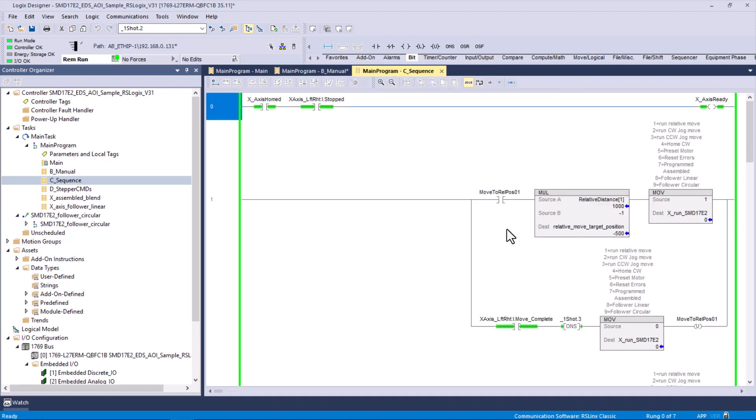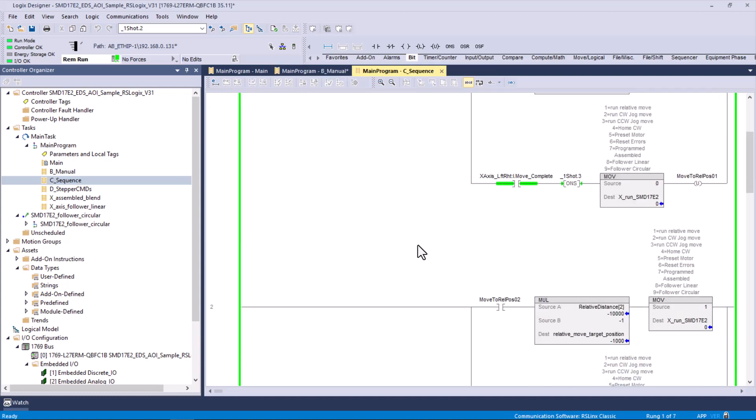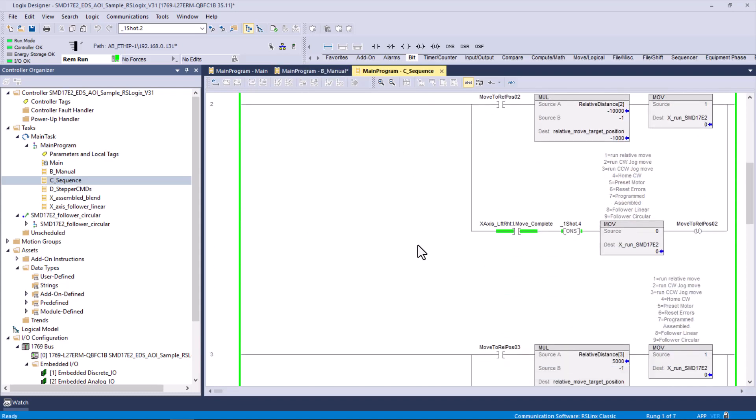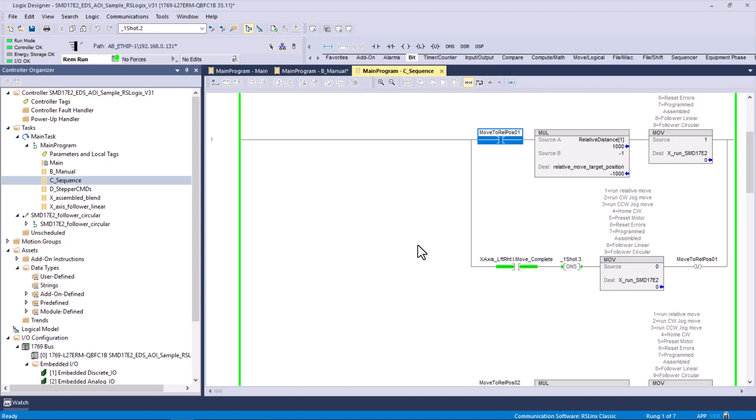Move to relative position one, which is 1,000. I'm multiplying by minus one. This will become minus 1,000. You can't see it, but when I toggle this, the x-axis just jumped to 1,000. Remember, I was at 500, and I moved a relative move of 1,000. Now you're sitting at 1,500. I have three of those. They all work the same. Once you get a little piece of logic that works for you, just repeat it. This is relative position one, and keep in mind, because I'm using an array, a single dimension array for relative distance.